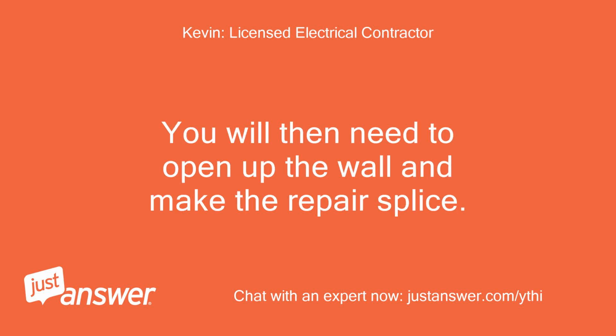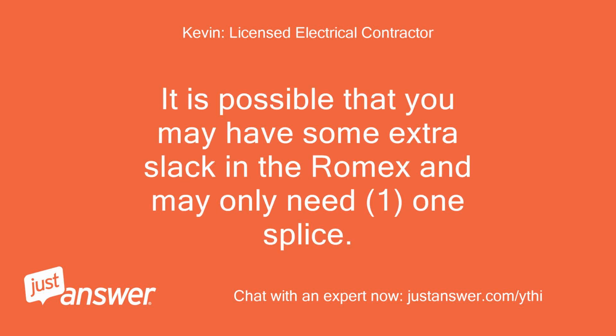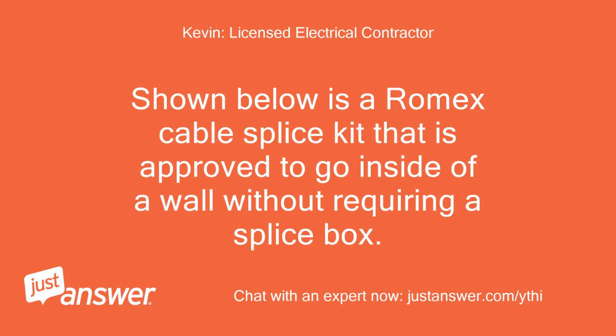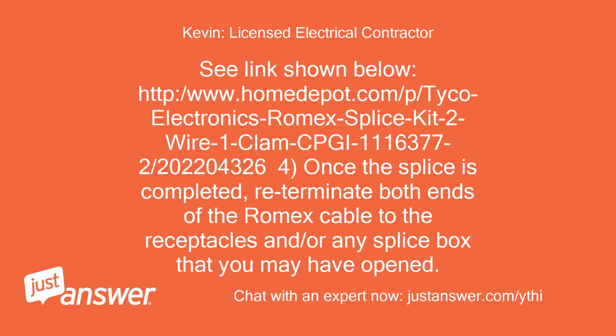You will then need to open up the wall and make the repair splice. It is possible that you may have some extra slack in the Romex and may only need one splice. Shown below is a Romex cable splice kit that is approved to go inside of a wall without requiring a splice box. See link shown below.